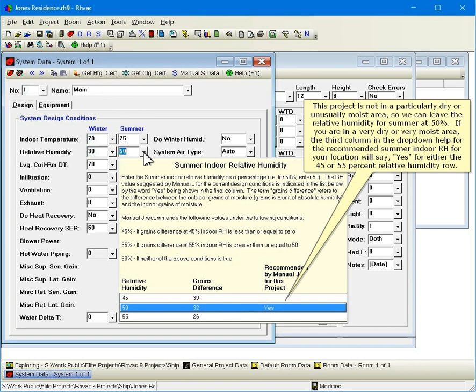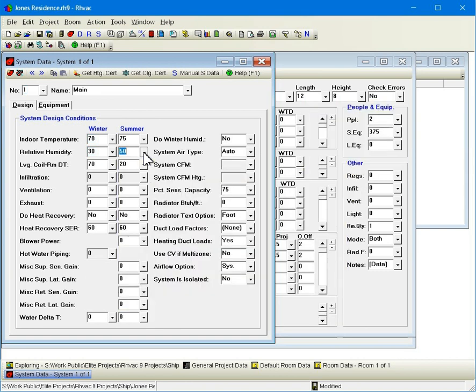This project is not in a particularly dry or unusually moist area, so we can leave the relative humidity for summer at 50%. If you are in a very dry or very moist area, the third column in the drop-down help for the recommended summer indoor relative humidity for your location will say yes for either the 45 or 55% relative humidity row.